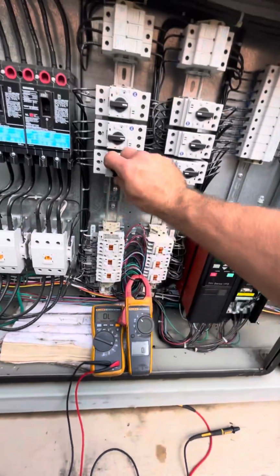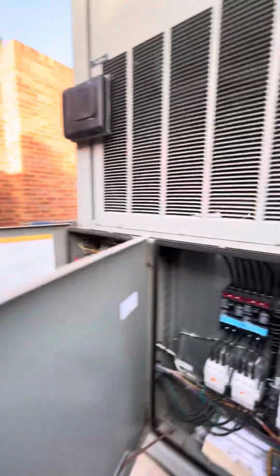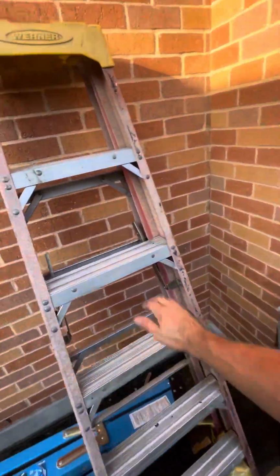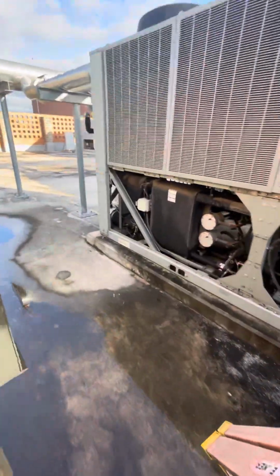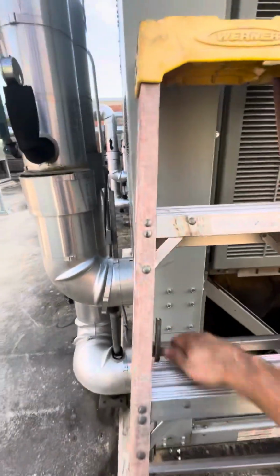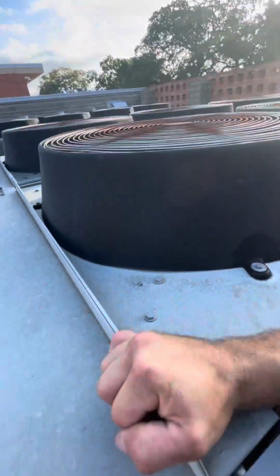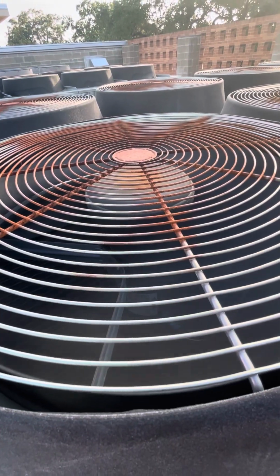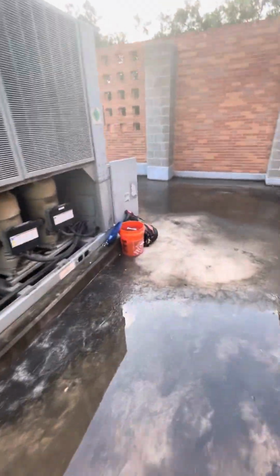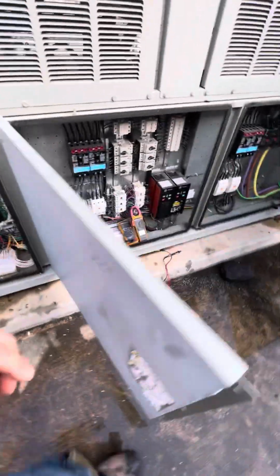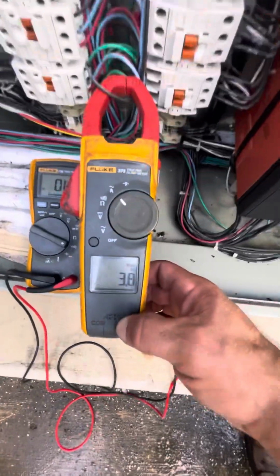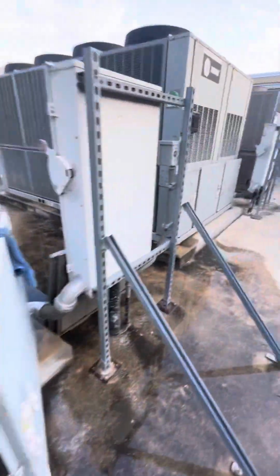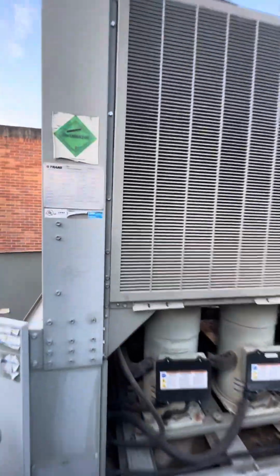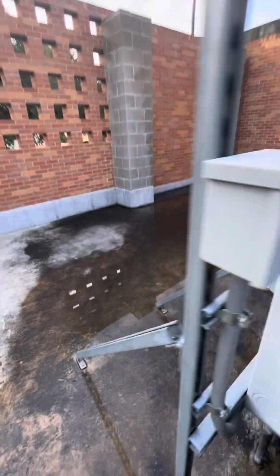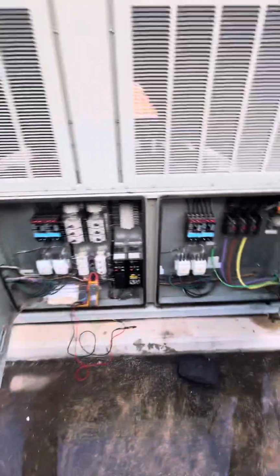It does pull higher than RLA, so we'll go ahead and enable that. You can hear that junky clunky fan motor back here. I don't think it has a soft ground on each of the legs, I think just because there's some voltage present. Now, even though this fan motor still works, I would say that it's not good. So there you go, some troubleshooting of condenser fan motors on small tonnage air-cooled chillers. And if you look here, we are getting over RLA. That to me is more important than picking up a little bit of ground trace. 3.2 FLA, we're over that, and as it continues to run, it's probably going to overheat, and that current reading is going to climb.